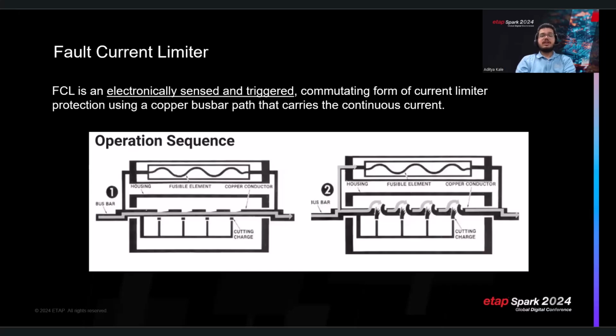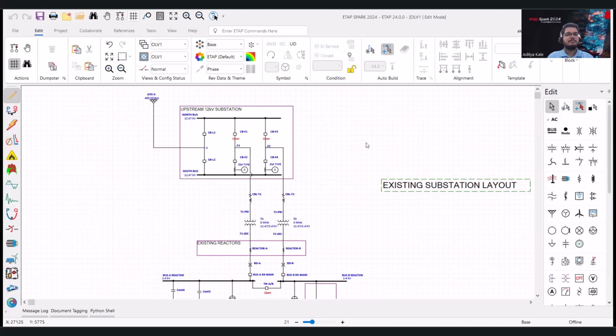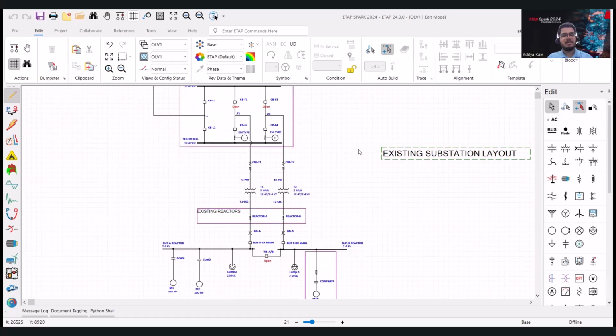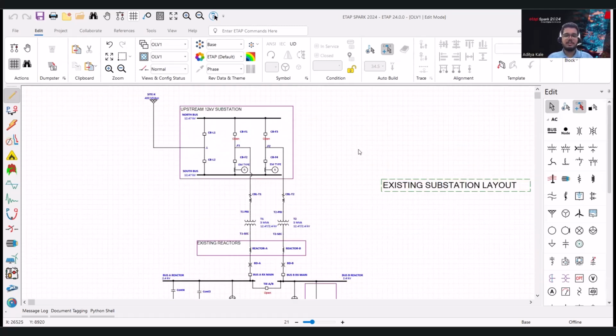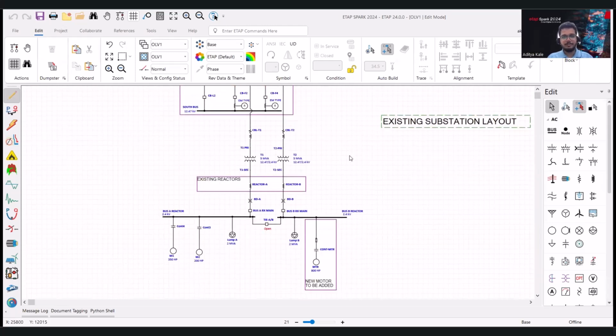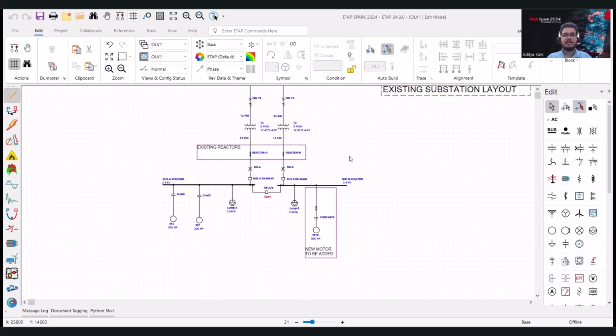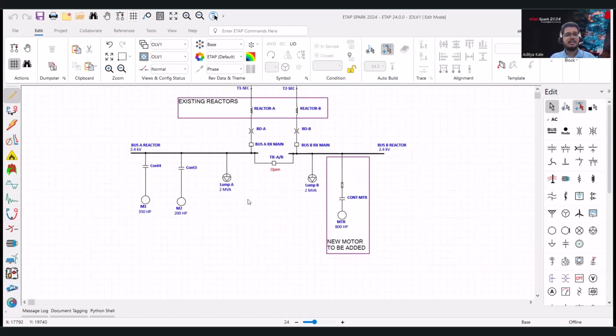Now, I think it is a good time to jump into the ETAP 2024 demo. So, here we have the ETAP 2024 demonstration for our project. We have a dummy model set up for this presentation. Let's look at it. We have an upstream 12 kV substation in a double bus, double breaker configuration, which feeds two transformers T1, T2, on the secondaries of which we have our reactors A and B, which are then feeding our substation. The substation is labeled bus A and bus B. We have the substation in a main tie main configuration.